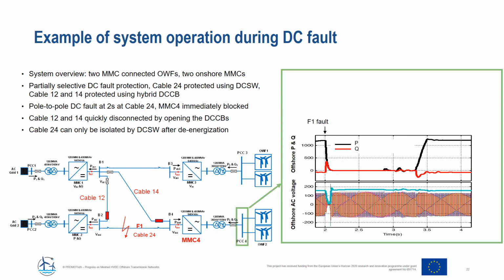So the DC fault causes the AC voltage and power generation from the wind farm to quickly reduce to zero. The offshore AC circuit breaker opens and the offshore wind farm becomes islanded. So the wind turbines are switched to grid forming control as previously described, and the offshore system voltage is quickly restored.